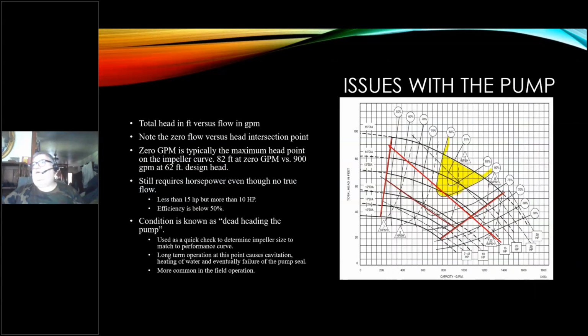So let's talk again about total head and flow versus GPM. Zero flow, note the zero flow versus head intersection point. This is head, okay? Zero flow, right? And maximum pump head. That's zero flow at the maximum. If you shut the valve off on the discharge of the pump, this is what you ought to see. This is actually a test to see if you've got the right size pump, if you're dealing with the right size impeller. So in the 14-inch, I should see 83, 82 feet of head at zero flow.